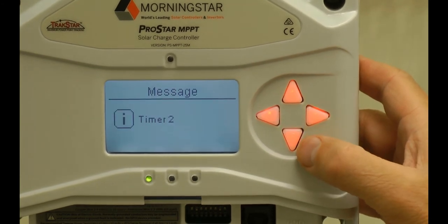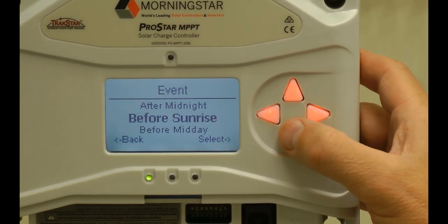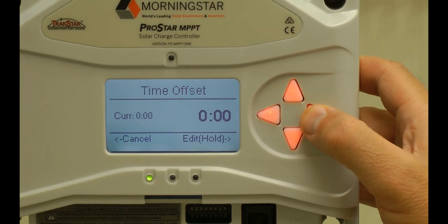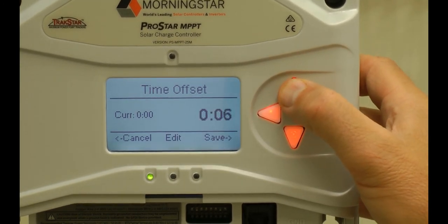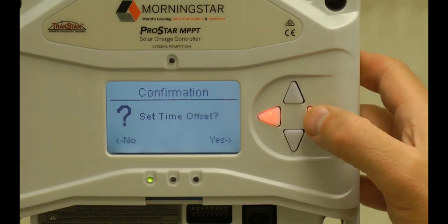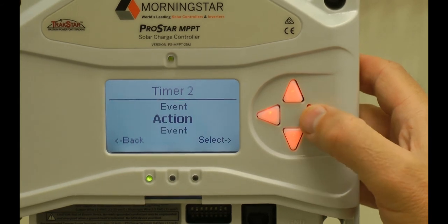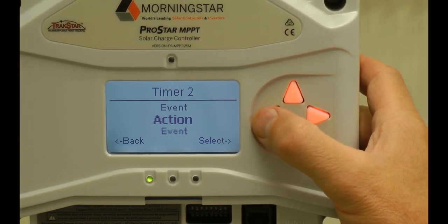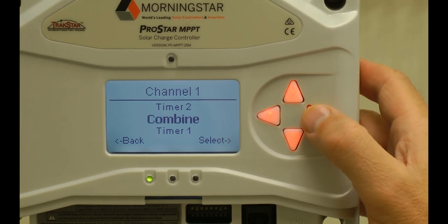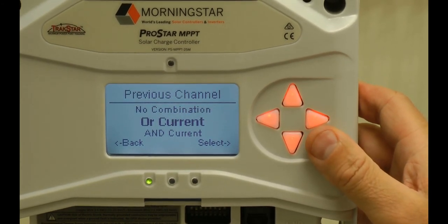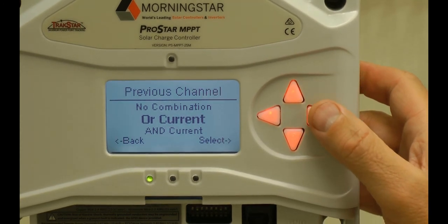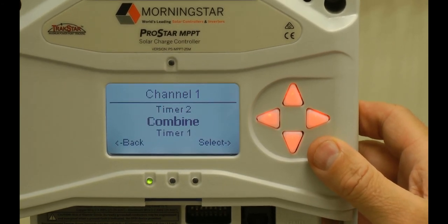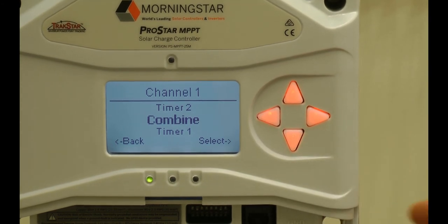Now we're going to set timer two. The event is going to be after sunrise, and the time is going to be 30 minutes — so we will set this to 30 minutes and save. The action is to turn the lights off. Now that we have both timers set, we'll go back and combine them. We're going to set them to combine as an OR function, meaning one or the other will trigger the event. That's it for channel one, timers one and two — we now have our sunrise lights on and off program.